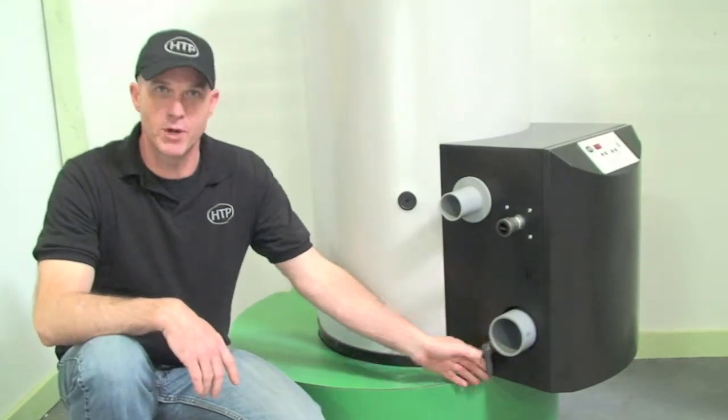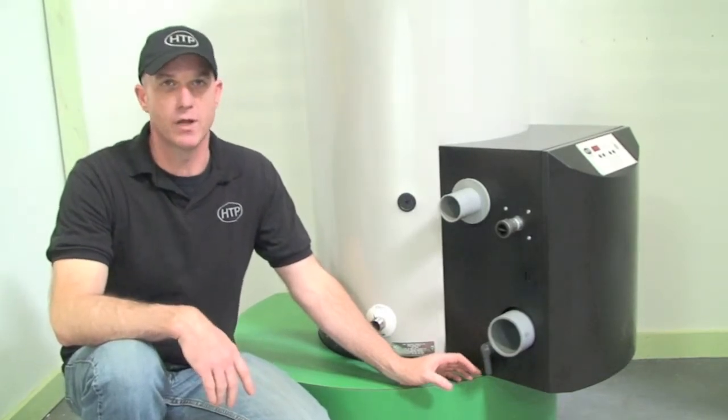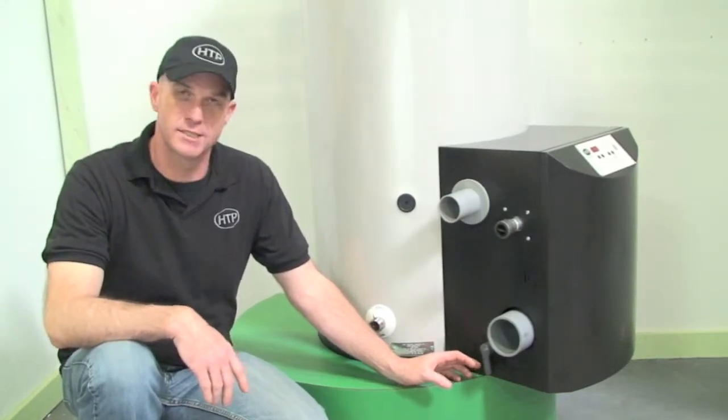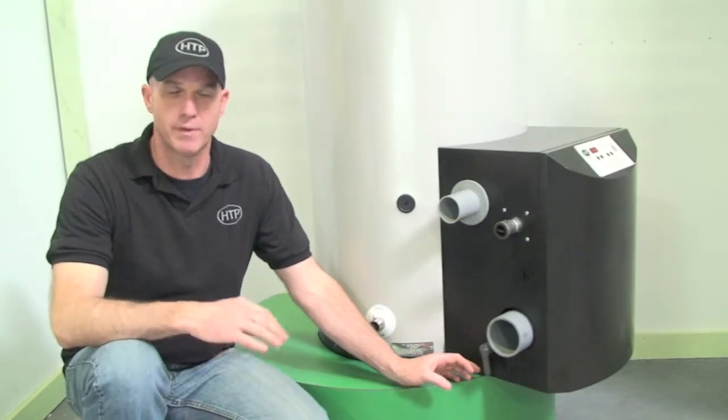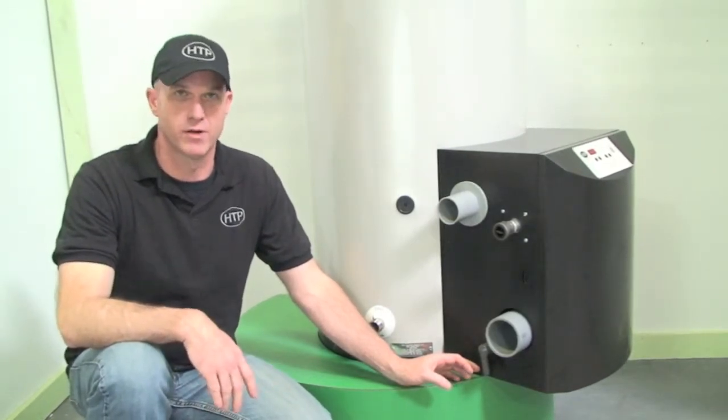In some areas they may have you drain it into a common drain, and in those cases you're going to need a condensate neutralizer. That takes the acidity out of the water, makes it neutral, and makes it safe to dump into drains. It will not rot the waste pipe and cause any further damage.